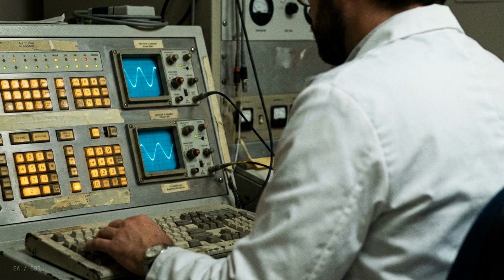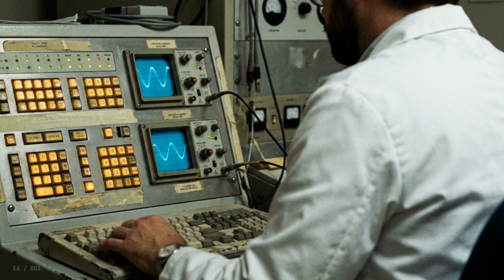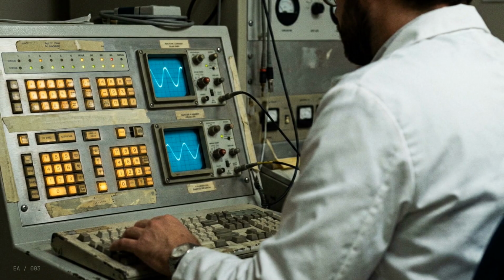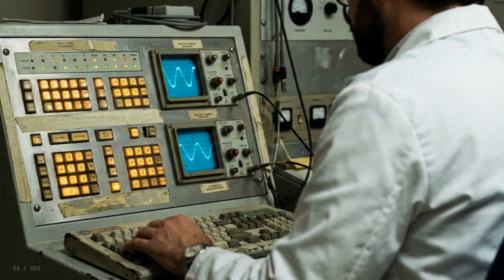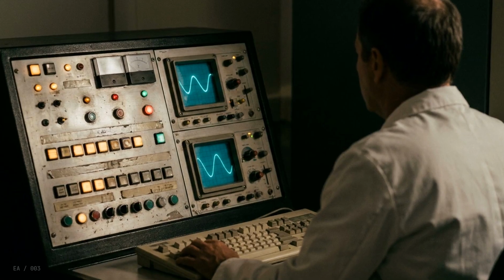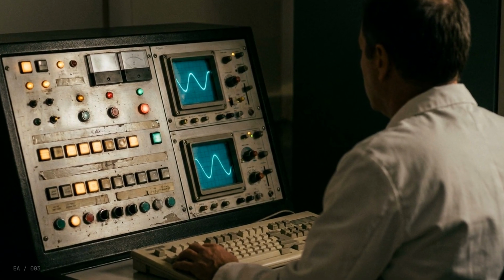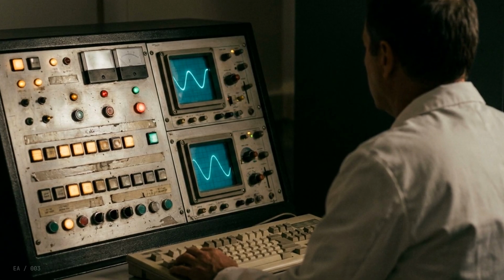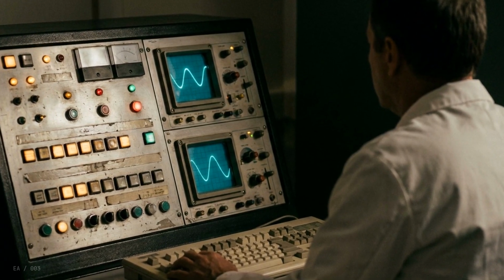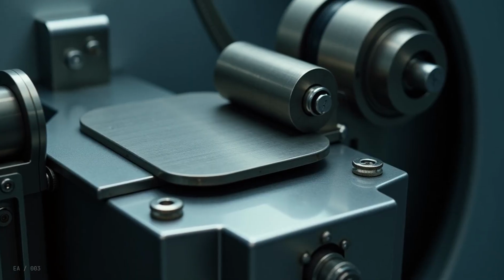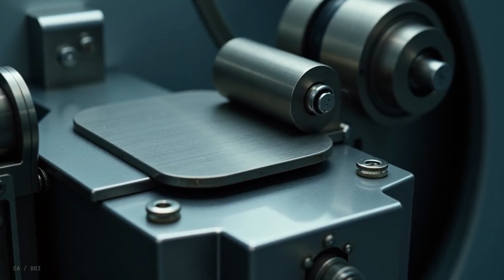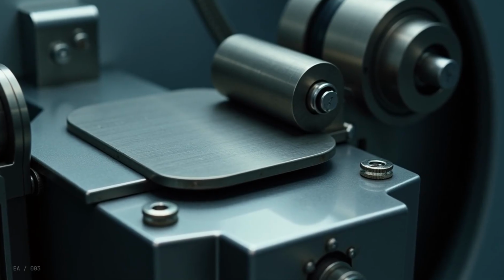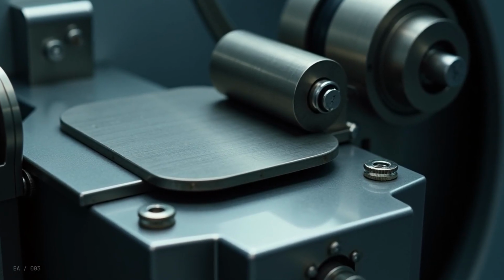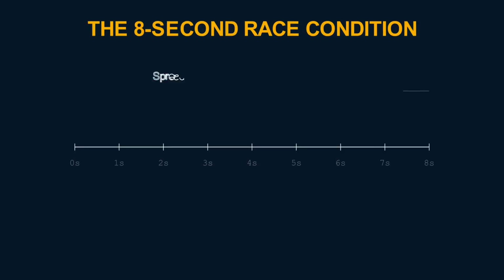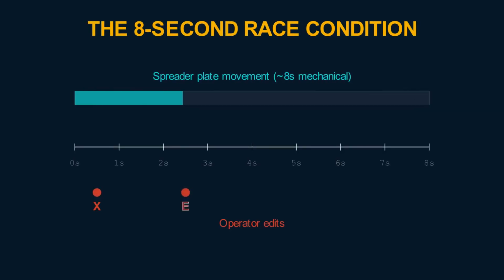The code had been maintained for many years by a single programmer. By 1985, that programmer had left the company. AECL could not locate him to ask questions about how specific subroutines worked. The software did 2 things relevant to this story. First, when an operator selected a treatment mode at the console, the software queued a command to move the spreader plate. The plate began moving. While it moved, the operator was allowed to continue entering parameters, energy level, dose, duration, anatomical site.